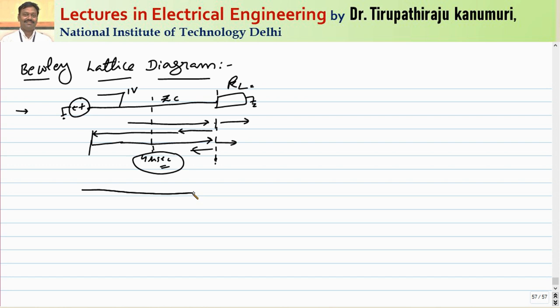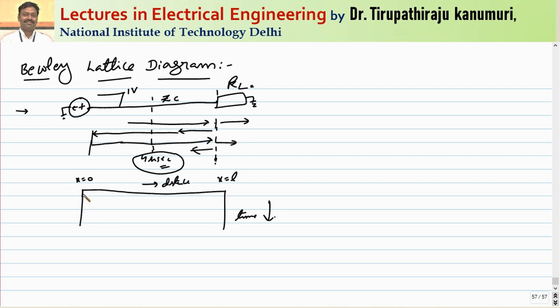In the Bewley lattice diagram method, the X-axis is along the distance, starting from X=0 and going up to X=L at the terminal. The Y-axis represents time. If a wave is transmitted at time t=0, it takes some time to reach the far junction. Assuming it reaches in time t seconds, it has a magnitude of 1. Some part is then reflected back and some part is transmitted to the load.